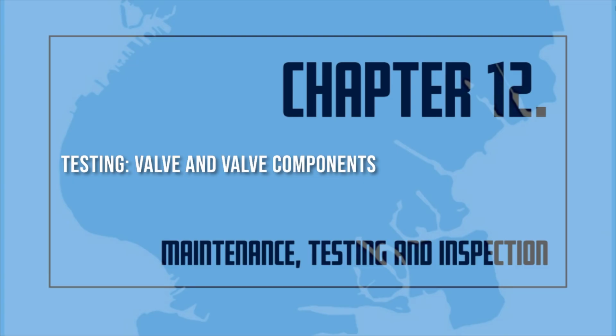Low air pressure alarms shall be tested quarterly in accordance with the manufacturer's instructions. Quick opening devices shall be tested quarterly following the following procedures. Close the system control valve, open the main drain valve and keep it in the open position. Verify that the quick opening device control valve is open.